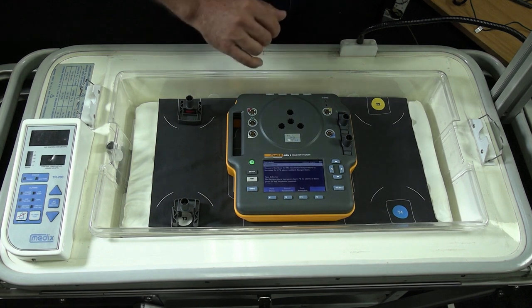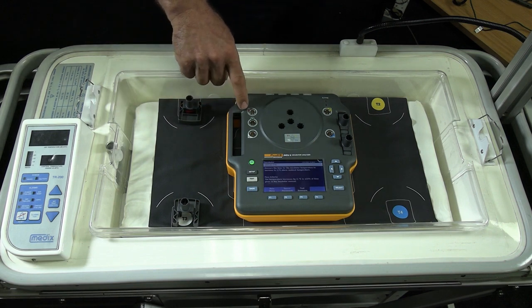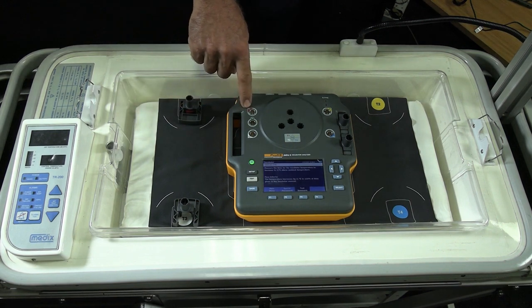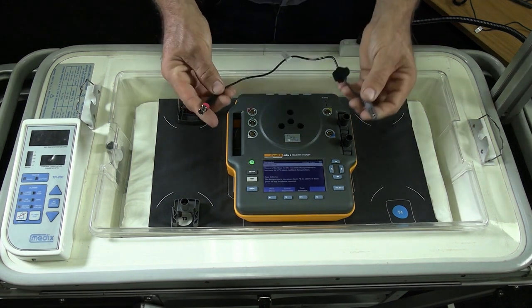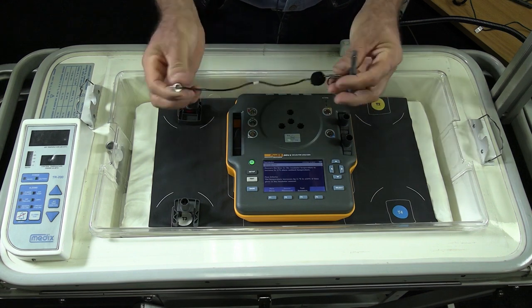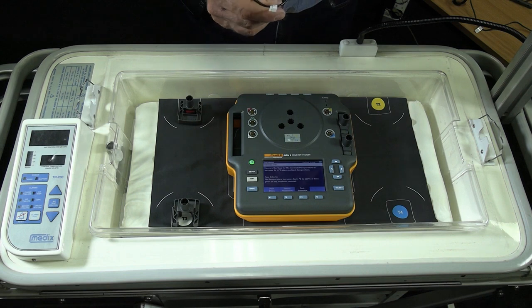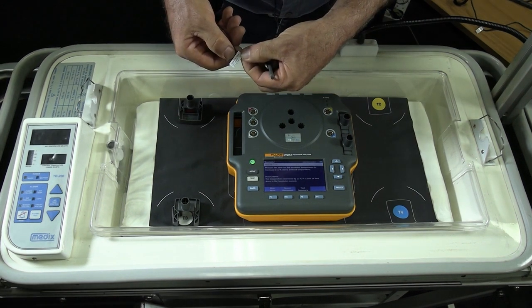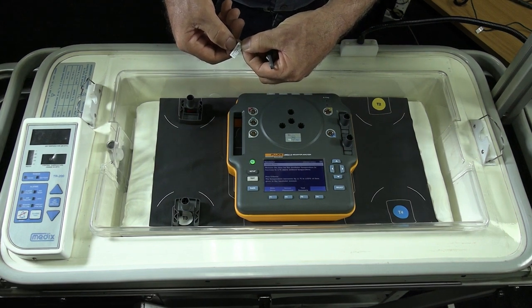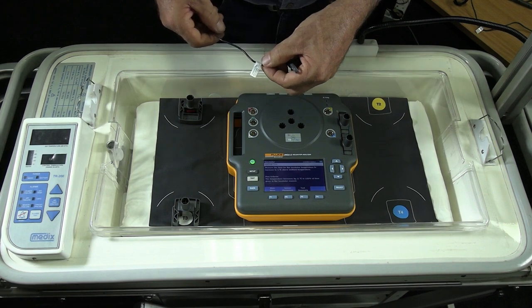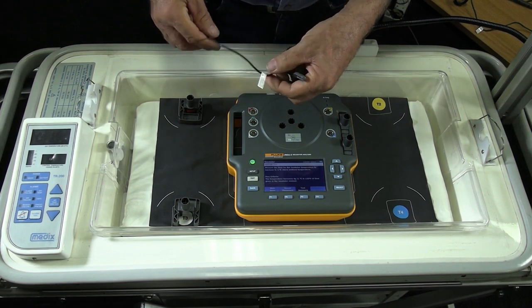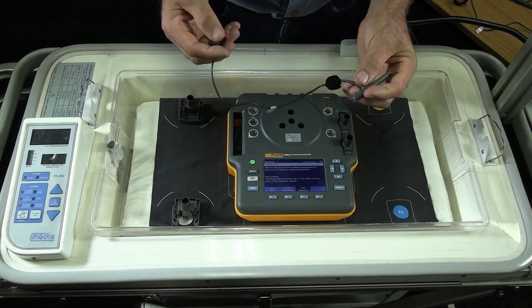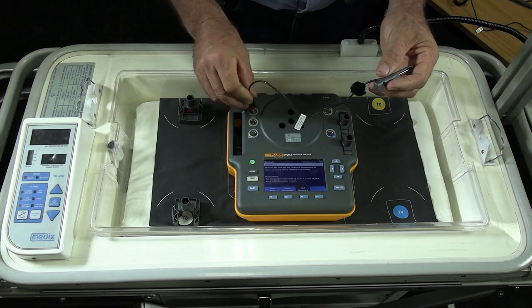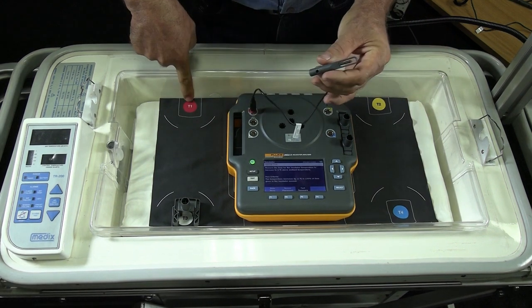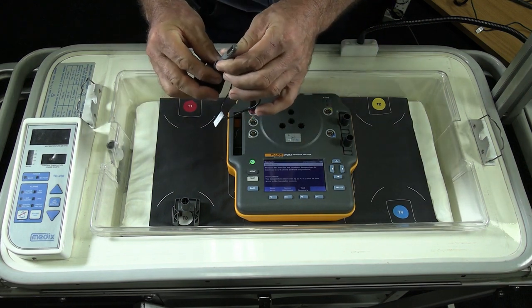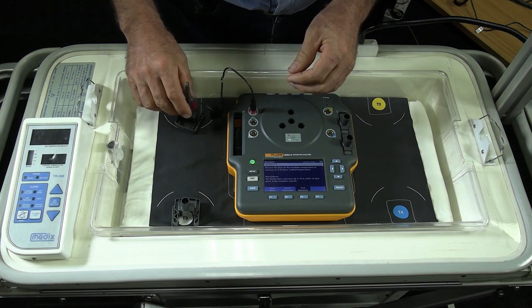Okay. So starting with the sensors, T1, you can see that T1 has got a red logo next to it. So what we do is we find T1, you'll see the red on it, and you will also see that it is a temperature probe. The reason I show you that you must read temperature probe is that we have different probes available here. We have sound probes, humidity probes, airflow probes, and temperature probes. And on some of them, the color coding might be the same. So this is red going to red. And T1, as we saw, T1. So what you do is you place the sensor inside your little stand and you put it in position.